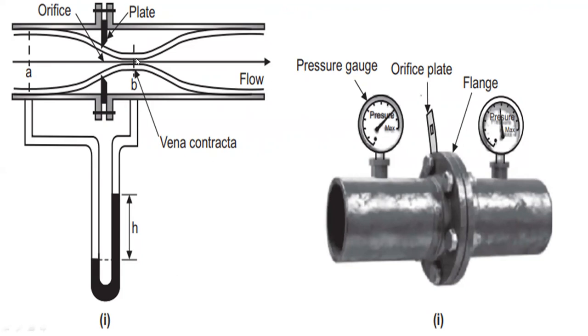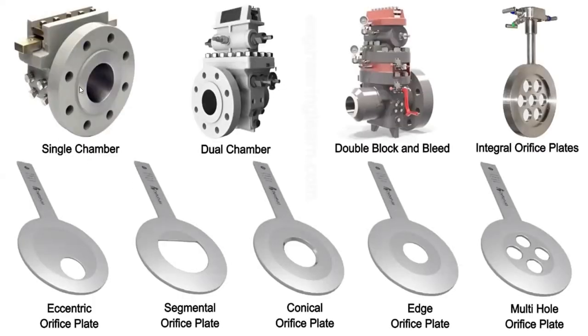The area of the orifice is far smaller than the cross-sectional area of the pipe. The flow from the upstream converges until a section downstream of the orifice plate is reached — the vena contracta. One arm of the U-tube manometer is connected upstream, and the other near the vena contracta. There are several types of orifice plates: single chamber, dual chamber, double block and bleed, integral, eccentric — where the orifice is not exactly at the center — segmental, conical, edge, and multi-hole orifice plates.